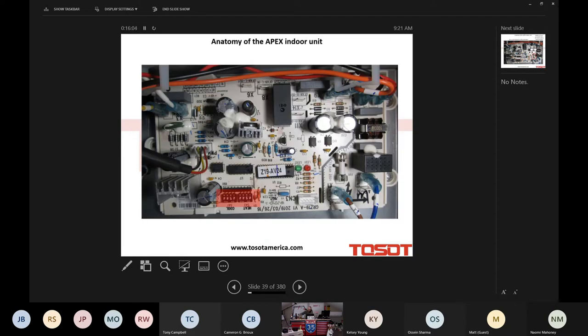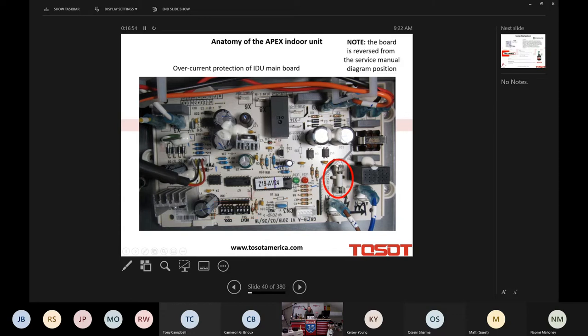Here is the control board of the indoor unit, guys. And I have one here, and we'll refer to that a number of times throughout the day. The first thing you should notice is that it's upside down. And that's not a problem with the picture. I didn't orient it incorrectly or anything like that. What you see, my friends, is what you get in the actual unit. The boards, both indoor and outdoor unit, are upside down. I don't know why. Not sure there's a logical reason for it, but nonetheless, they are upside down. So just be aware of that. It's easily overcome in the field. We'll talk about that as we move forward.